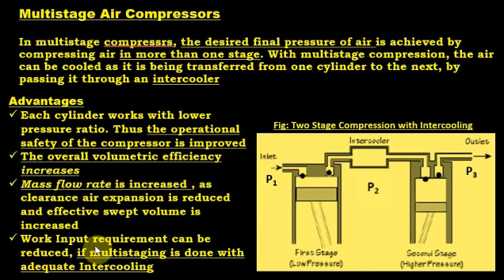Consider this PV diagram now. You have three pressure levels: the intake pressure level P1, the intermediate pressure level P2, and the final required pressure level P3. For the first stage compression, the volume of air taken in is, let us say, V1. For the time being, we neglect the clearance volume effect. Therefore, the volume taken in the first cylinder is V1 and it is compressed polytropically to the state 2 dash, that is to the pressure P2. The first stage compression follows the polytropic process, PV^n = constant, and 1 to 2 dash is that process.